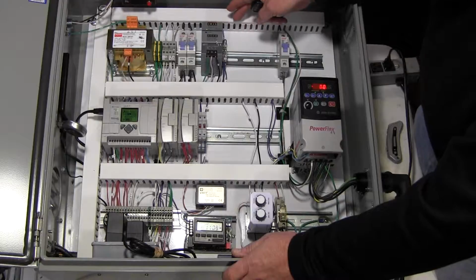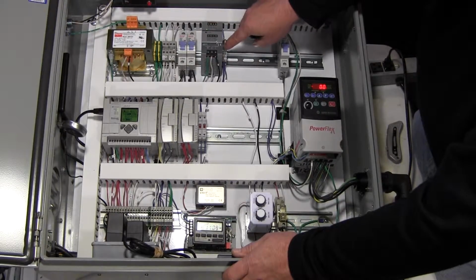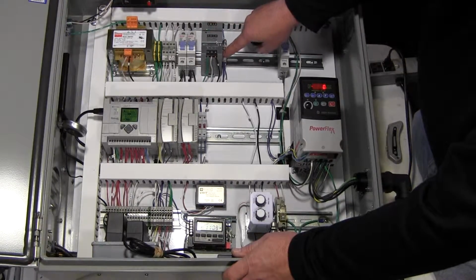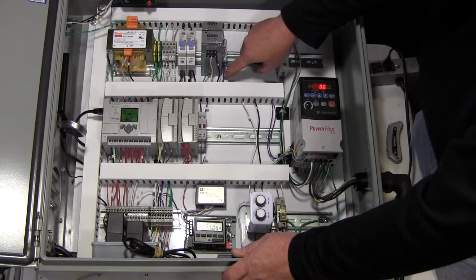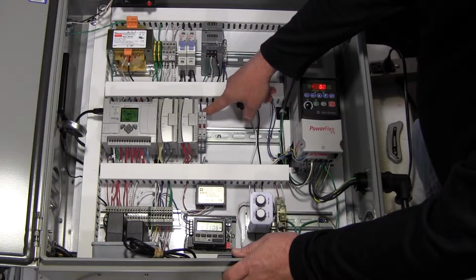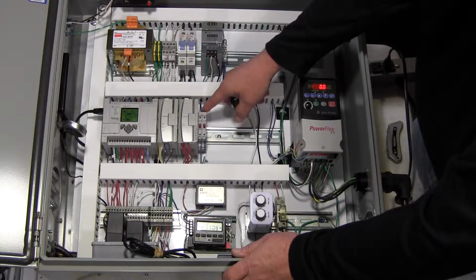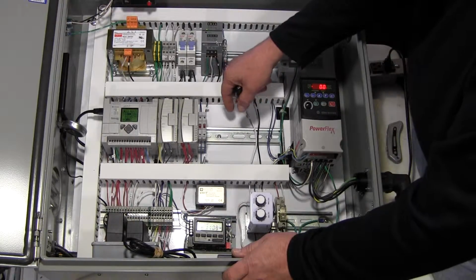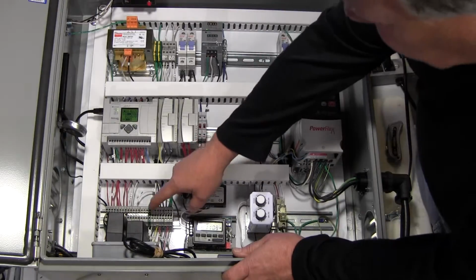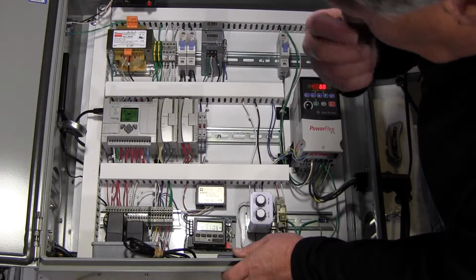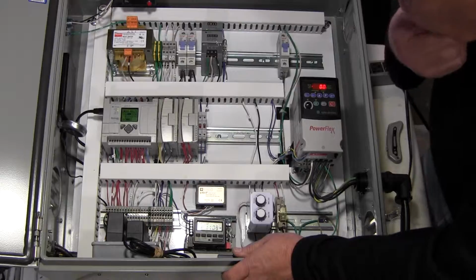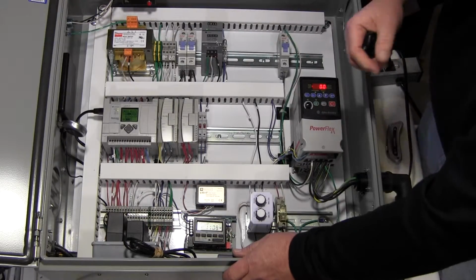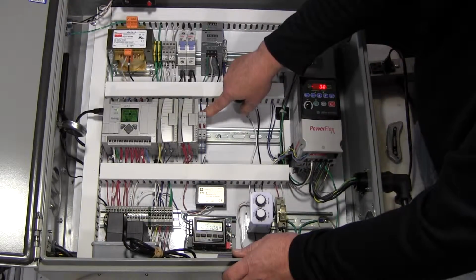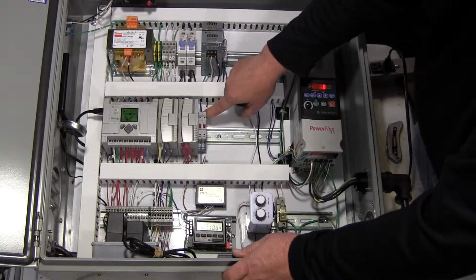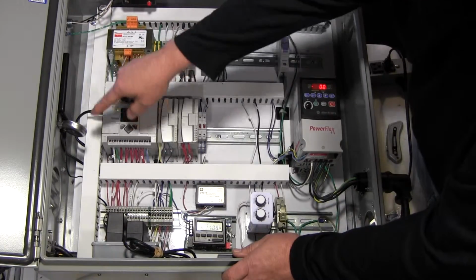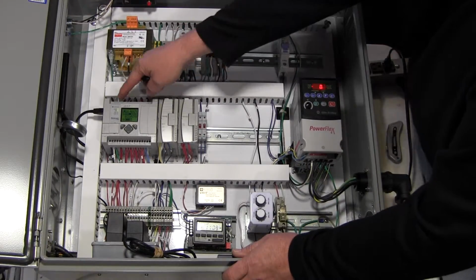The output of the 24 volts DC, the actual plus goes to this guy right here. This is the distribution point for the DC power, which would go into these toggle switches, and then also would go down here at this point to supply DC power to the transmitters in the pump package. So if you take a look at the power, this is the DC power coming in to these toggle switches.